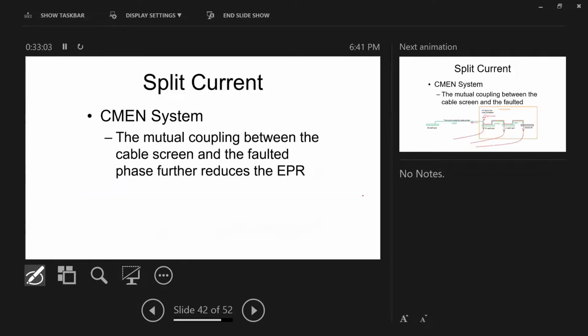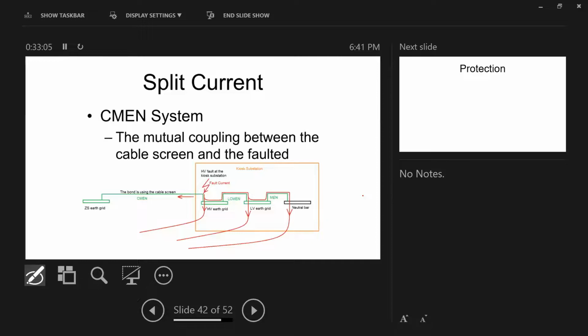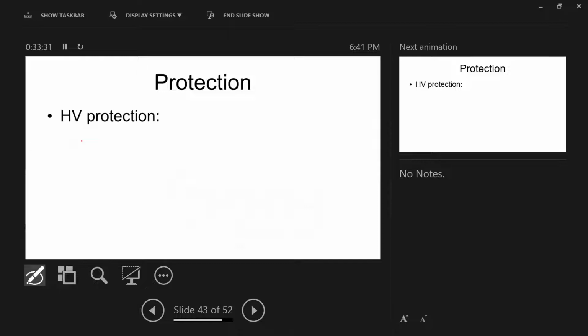If I have a common main earthing system, I connect this, and now under fault, I could have 90 or 95% returns. All this about the earthing system is to show you that without our earth being a solid part of our system, I cannot have a safe working environment. That's number one. Number two, protections.